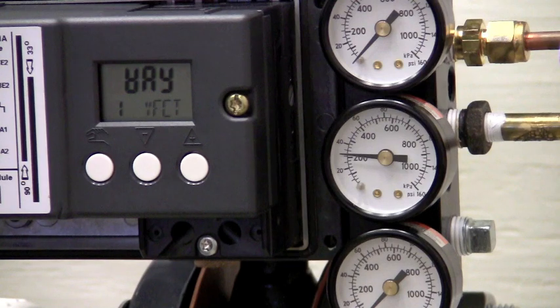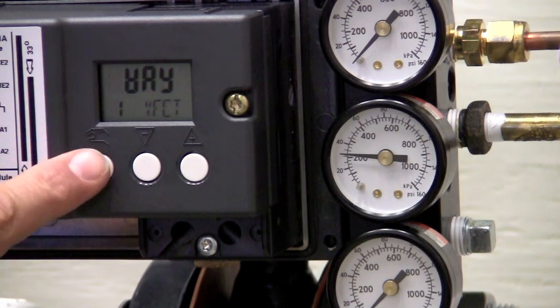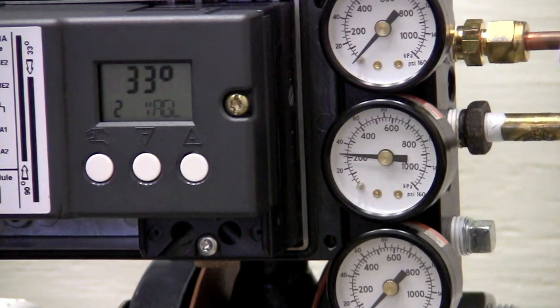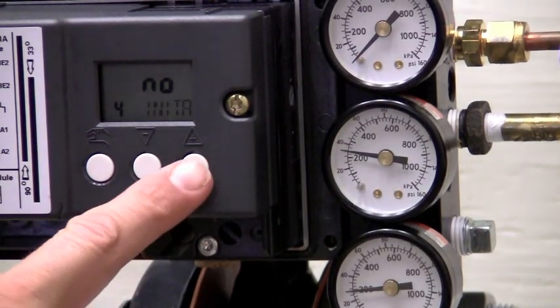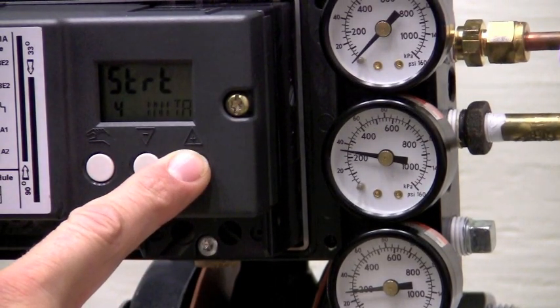The PS2 can be configured in a matter of minutes with the push buttons on the front of the unit. All you need to do is tell the PS2 three things: whether the valve is rotary or rising stem, if you're using the standard or special short stroke setting, and for rising stem applications, the length of the feedback arm.